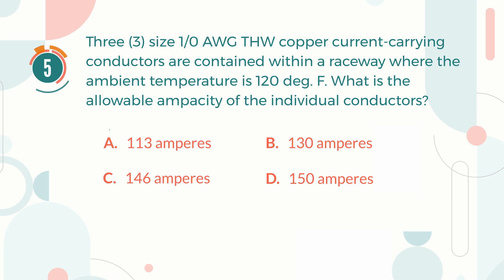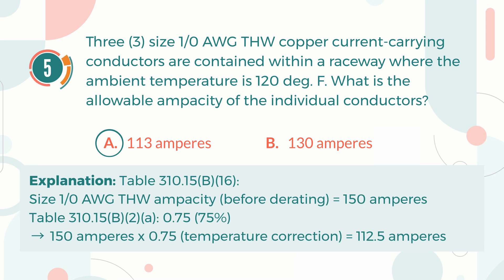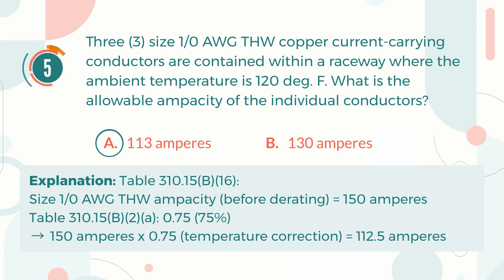The correct answer is A. 113 Amperes. Explanation: Following Table 310.15(B)(16), the ampacity of size 1/0 AWG THW before derating is 150 Amperes. Then, looking up Table 310.15(B)(2)(a) for the appropriate correction factor, with an ambient temperature of 120 degrees Fahrenheit, we have a factor of 0.75 or 75%. 150 Amperes multiplied by 0.75 equals 112.5 Amperes, rounded to 113 Amperes.